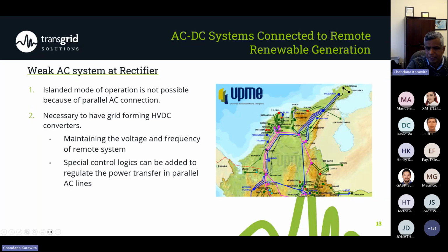converter. This is the common mode of operation in most of the available offshore systems right now. But when we have a parallel AC connection, we cannot do that, so we need properly designed grid forming converters. In our study for UPME about the HVDC link, the report is available online. You can see that we showed the grid forming HVDC converter can maintain the stability of the system. In addition, we can have special control logics to control the power transmission in the parallel AC lines as well. All these things are discussed in the report. That is one of the requirements for such a system.